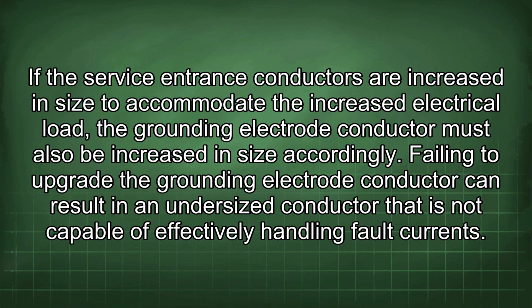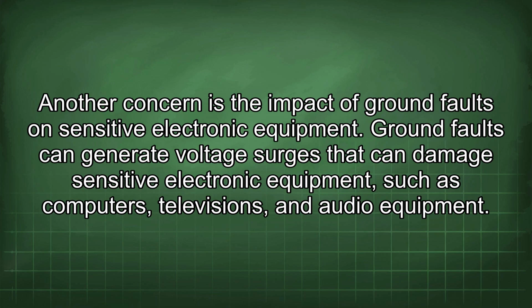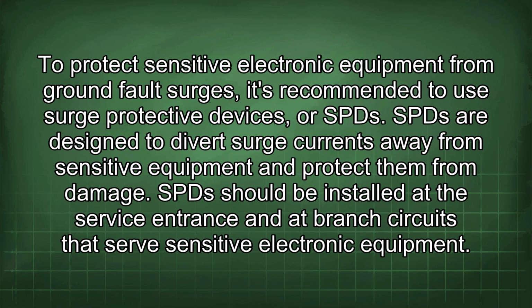Another concern is the impact of ground faults on sensitive electronic equipment. Ground faults can generate voltage surges that can damage sensitive electronic equipment, such as computers, televisions, and audio equipment. To protect sensitive electronic equipment from ground fault surges, it's recommended to use surge protective devices, or SPDs. SPDs are designed to divert surge currents away from sensitive equipment and protect them from damage. SPDs should be installed at the service entrance and at branch circuits that serve sensitive electronic equipment.